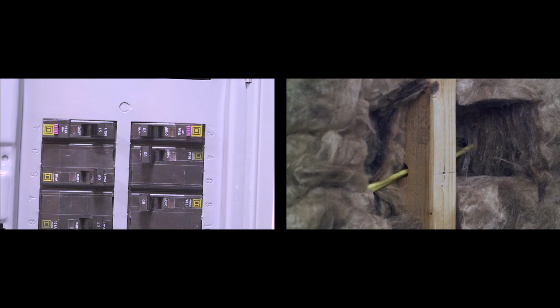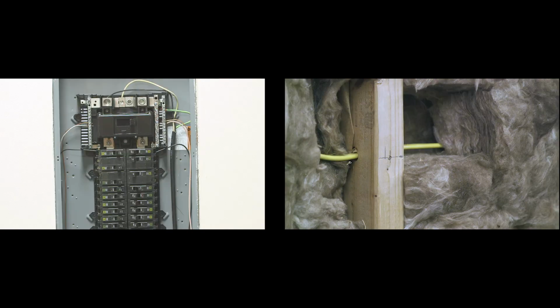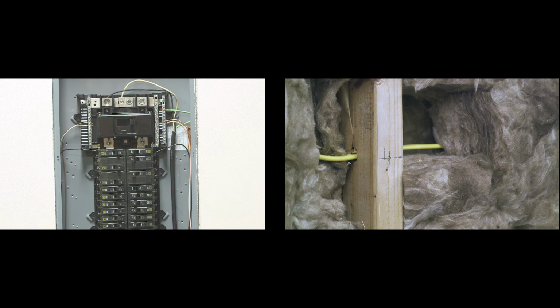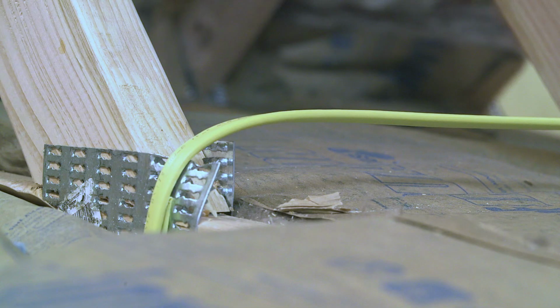In the first test, the AFCI circuit breaker trips and no fire occurs inside the wall. In the second test, the standard circuit breaker is the only protection for arcing faults. As you can see, when the screw penetrates the NM cable, the standard circuit breaker does not trip and a fire occurs. The second model tested replicated a potential attic wiring scenario.